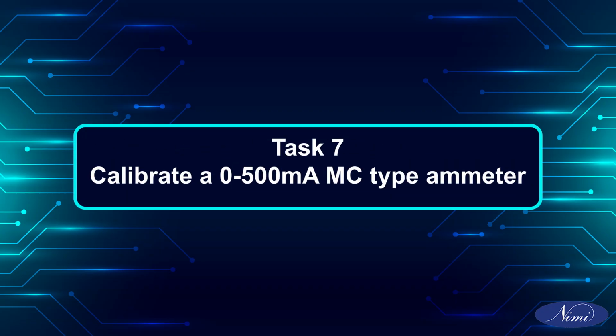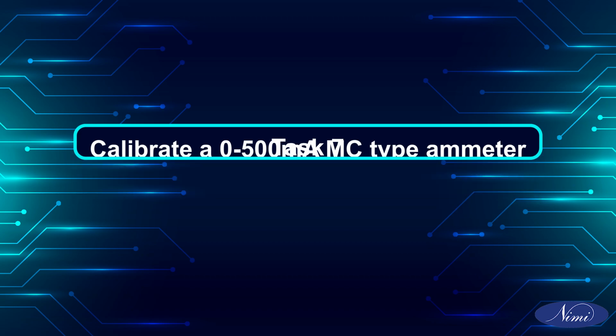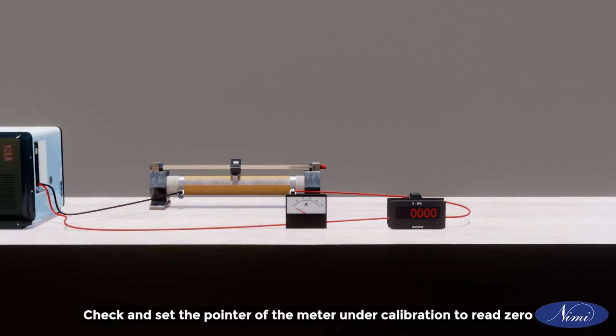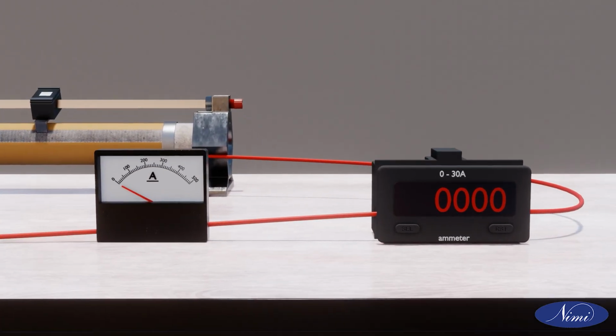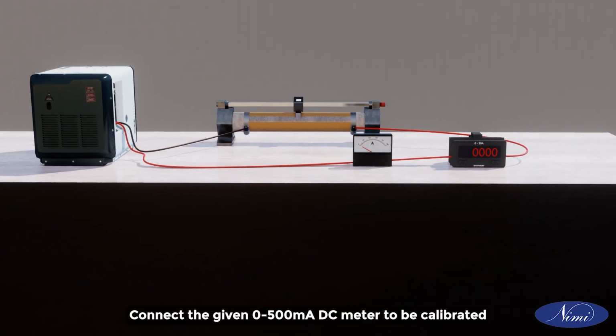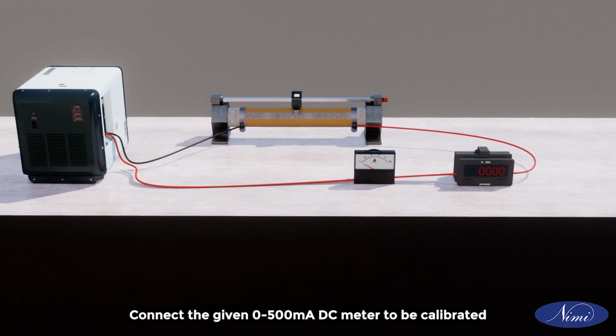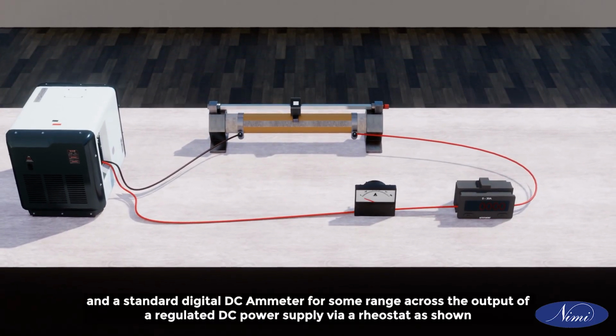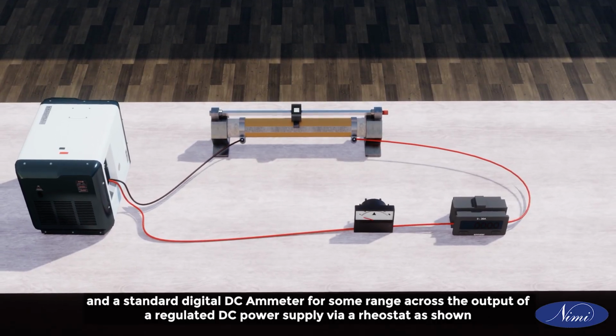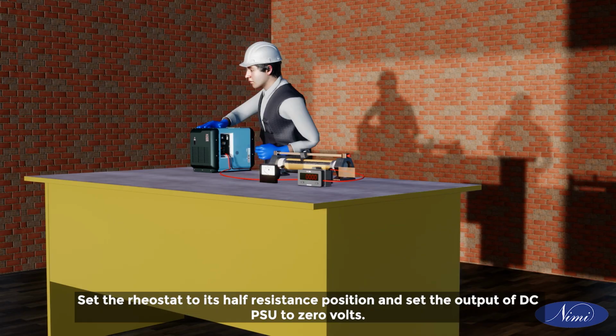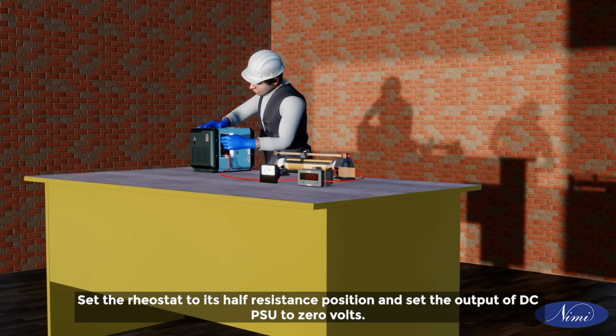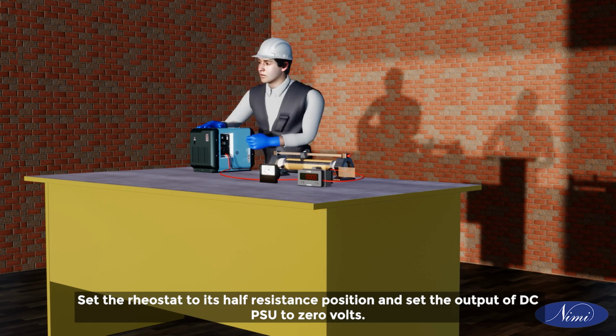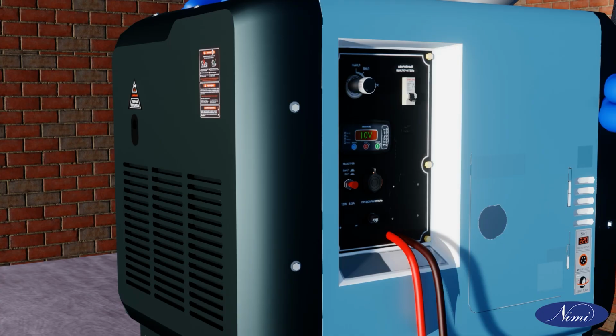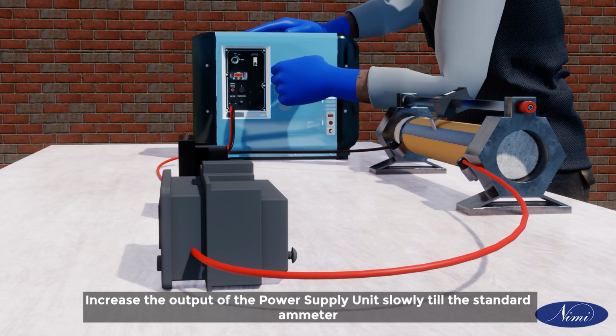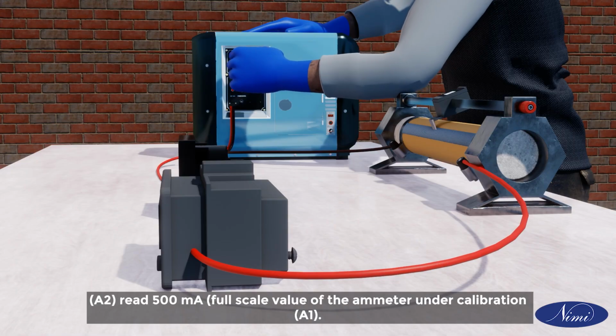Task 7. Calibrate a 0 to 500 mA MC-type ammeter. Check and set the pointer of the meter under calibration to read 0. Connect the given 0 to 500 mA DC meter to be calibrated and the standard digital DC ammeter for some range across the output of a regulated DC power supply via a rheostat as shown. Set the rheostat to its half resistance position and set the output of DC PSU to 0 volts. Increase the output of the power supply unit slowly till the standard ammeter A2 reads 500 mA, full-scale value of the ammeter under calibration A1.